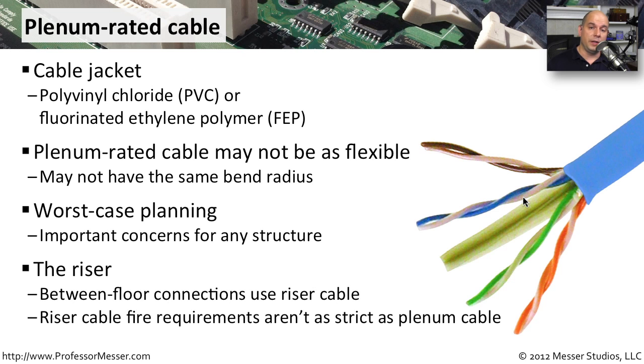If you have cable going between floors, you might use a different type of cable specifically designed for the riser — the connection between those floors. In a riser situation, there is usually a fire block or physical firewall in place to limit fire moving between floors. So riser cable doesn't have quite the same strict requirements as plenum cable, but there is still a consideration to limit the impact if there was ever a fire.